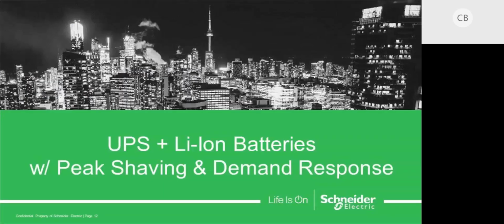Thank you, Karsten. So when we talk about these microgrid solutions, one of the things we want to share is a new offer where we can utilize a UPS system combined with lithium-ion batteries to allow peak shaving and demand response. This is a new feature. It just requires a simple software update on the UPS system, and it'll allow you to use the batteries on these UPS systems to provide some peak shaving capability. So, Karsten, if you go to the next slide.